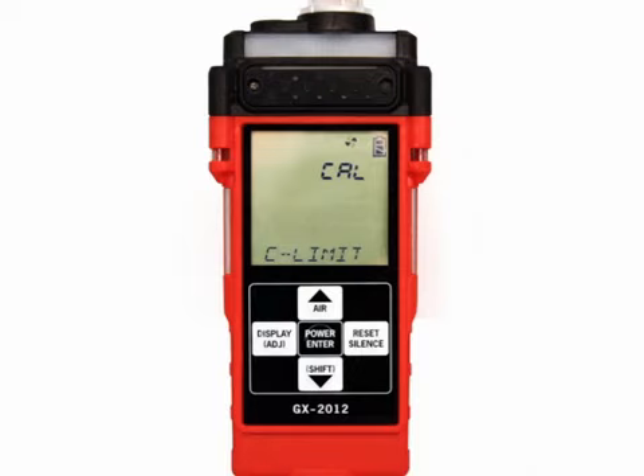If the calibration reminder item in maintenance mode is turned on, the screen that appears next depends on how the calibration expired item is set. If the unit is due for calibration and the cal expired is set for confirm to use, then the cal limit prompt will display and the alarm LEDs and buzzer will pulse several times. When this occurs, press and release the reset silence button.